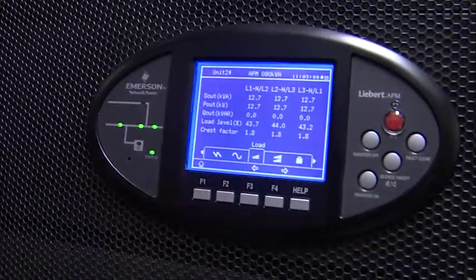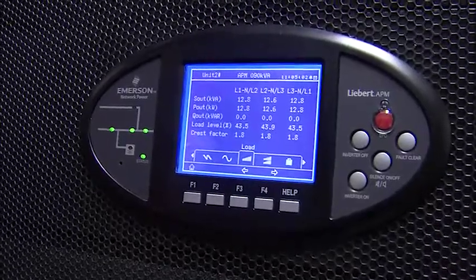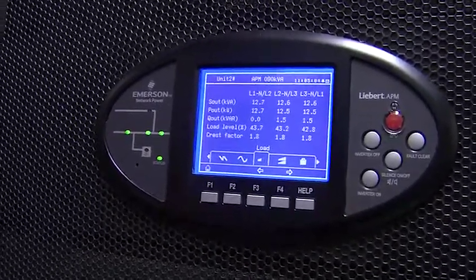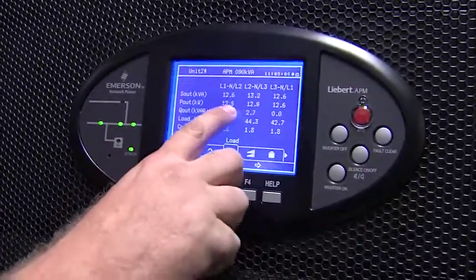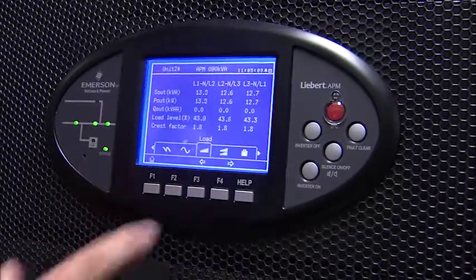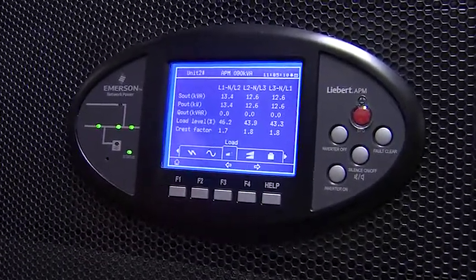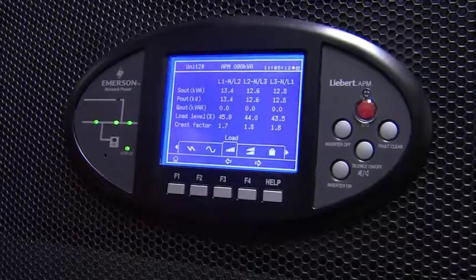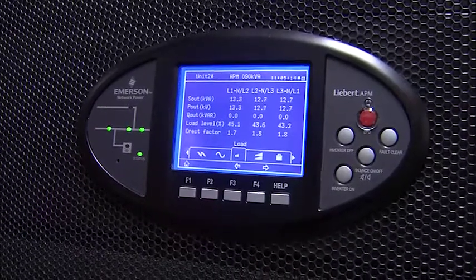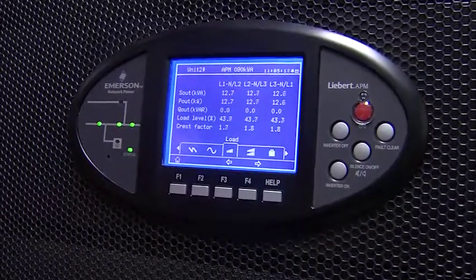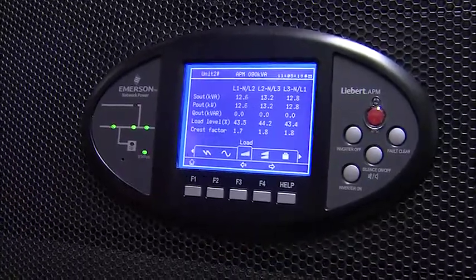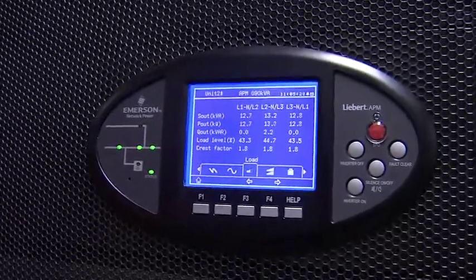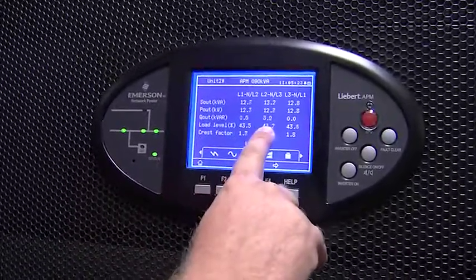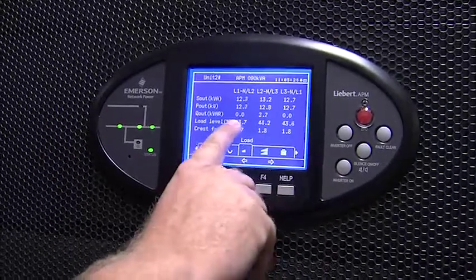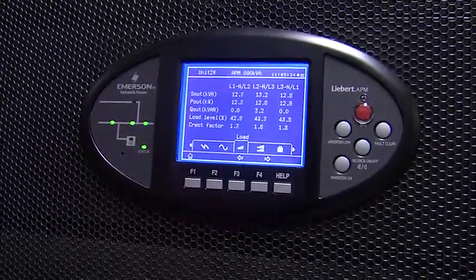Your kW is your true power draw. So we look here, and we're actually at unity. Our kVA and our kW should always be equal. A lot of times you'll have a power factor correction. These boxes don't have that. They don't need it. They're unity power factor. So our load level is 43%. Now I want to take you down to this unit real quick.